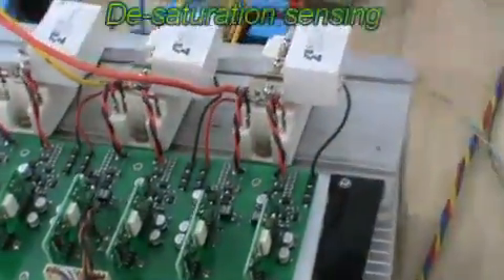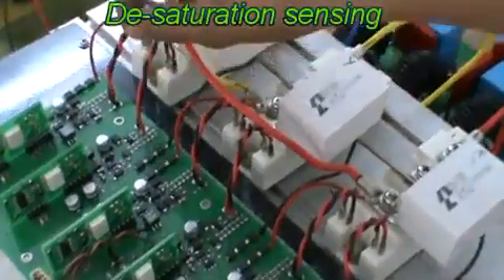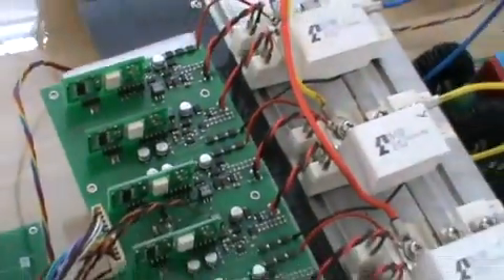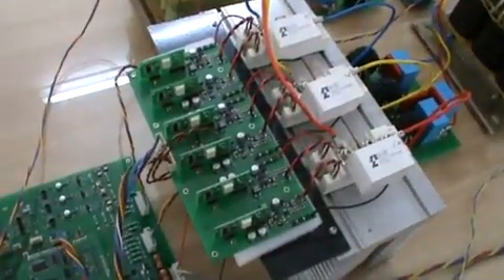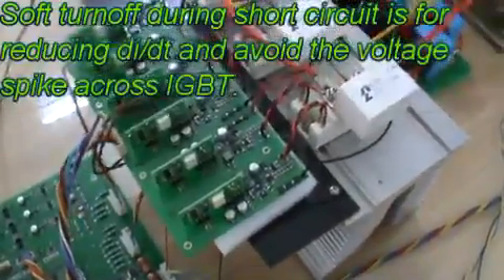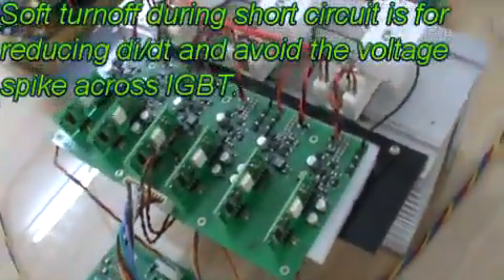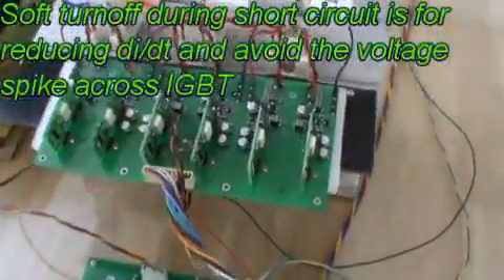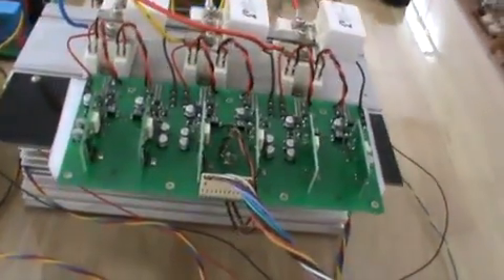These wires are connected to the collector of each IGBT module for desaturation sensing. During desaturation, a soft turn-off of IGBTs is provided. This will avoid high voltage spike across the collector and emitter of the IGBTs during turn-off.